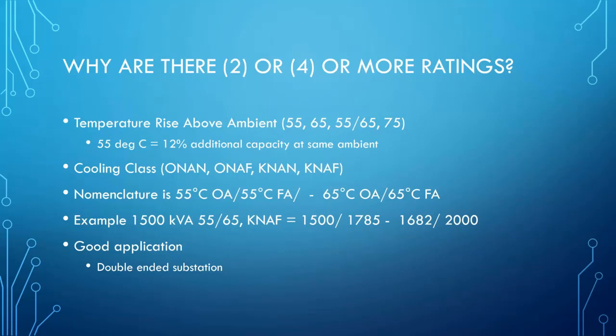Why are there so many ratings on a transformer? Why do I see two ratings? Why do I see four ratings, or sometimes even more ratings? Okay. In the liquid-filled transformer world, the ANSI standard is to manufacture a core and coil that, when it's fully loaded, will rise 65 degrees above the ambient temperature. And that has worked for many, many, many years.